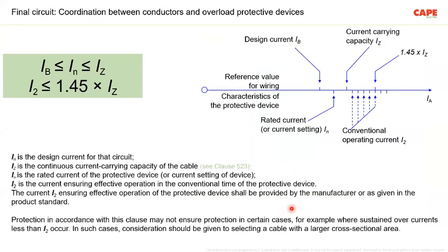The selection of conductors and the protective device at the final circuit is very, very important. About a week back, I was discussing with one of the customers. I asked, on what basis are you selecting the wire and the MCB? They told me, if we have a chiller which requires 32 amps, then we put a 63 amps MCB, and we put a wire which can handle maybe 35 amps of current. This is absolutely not the correct way.